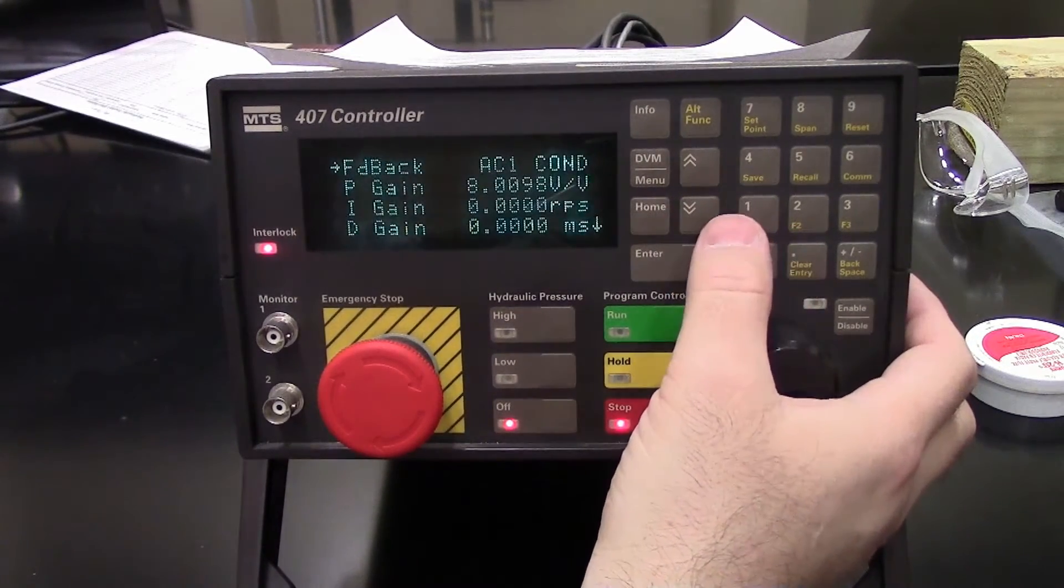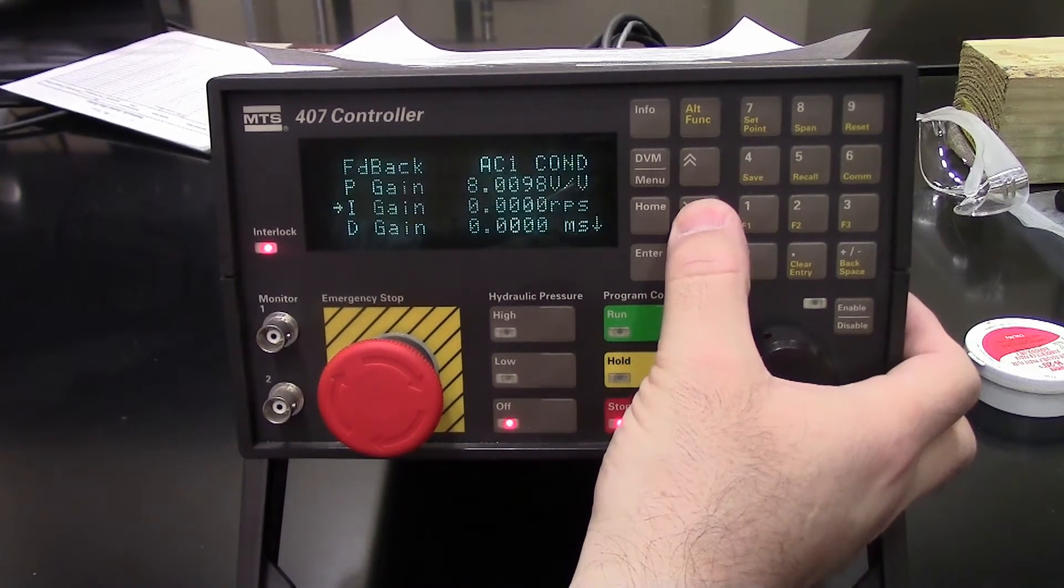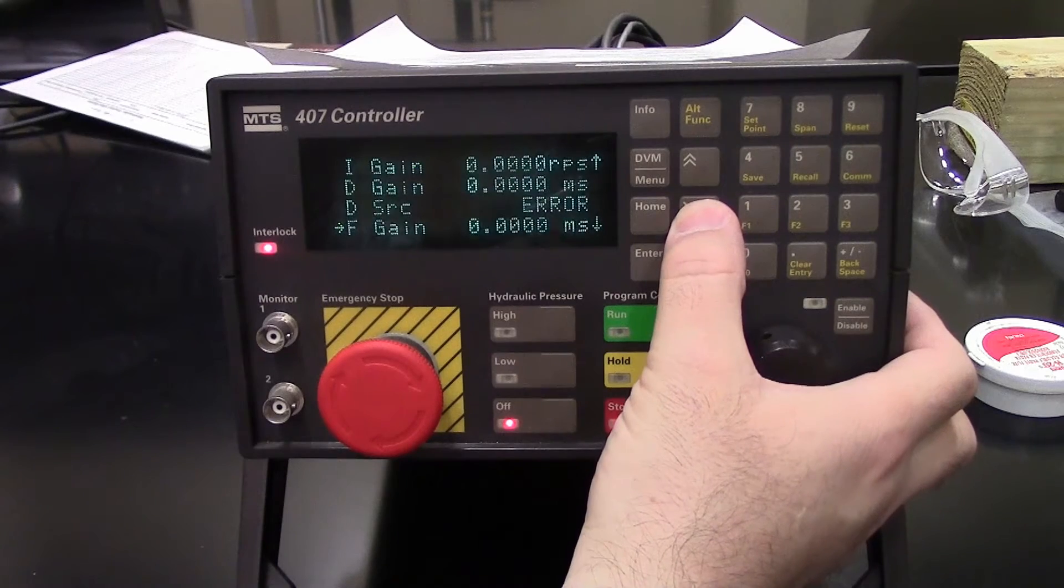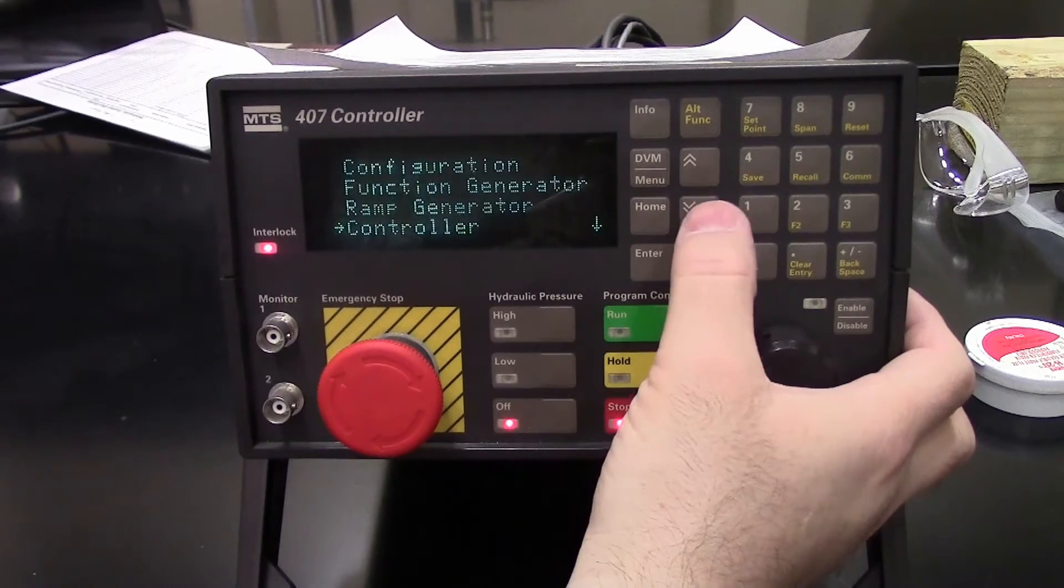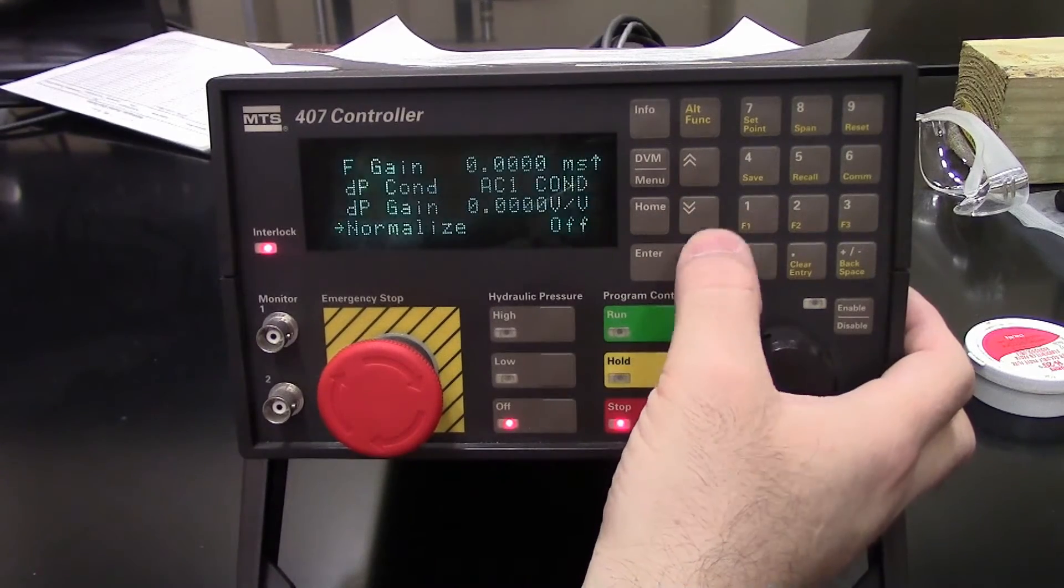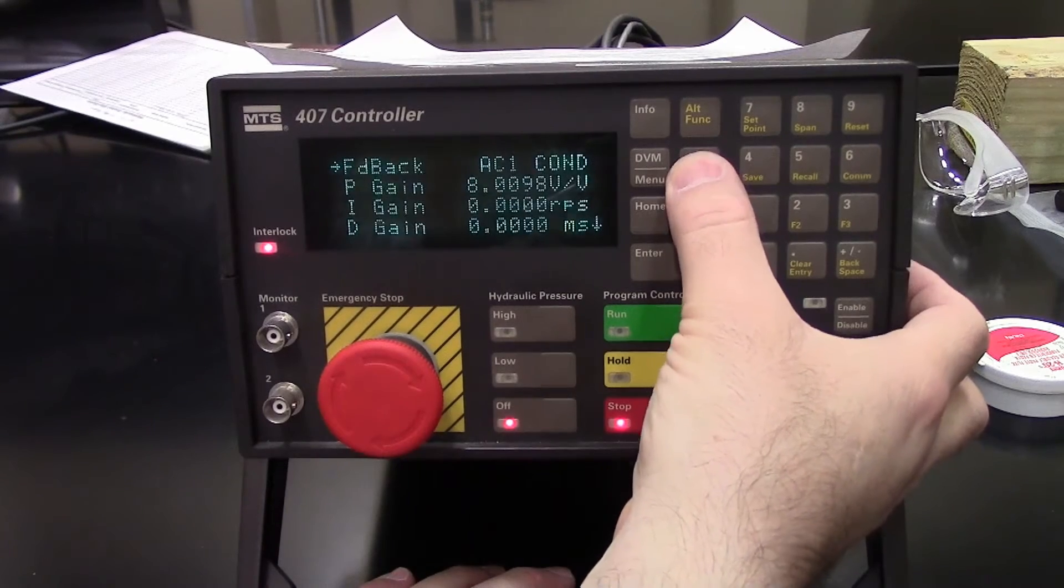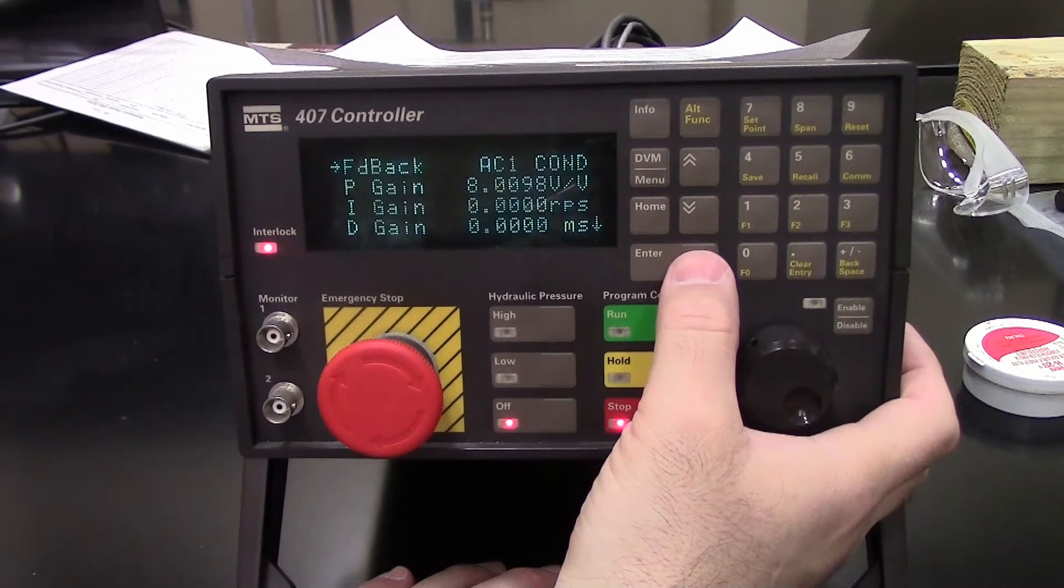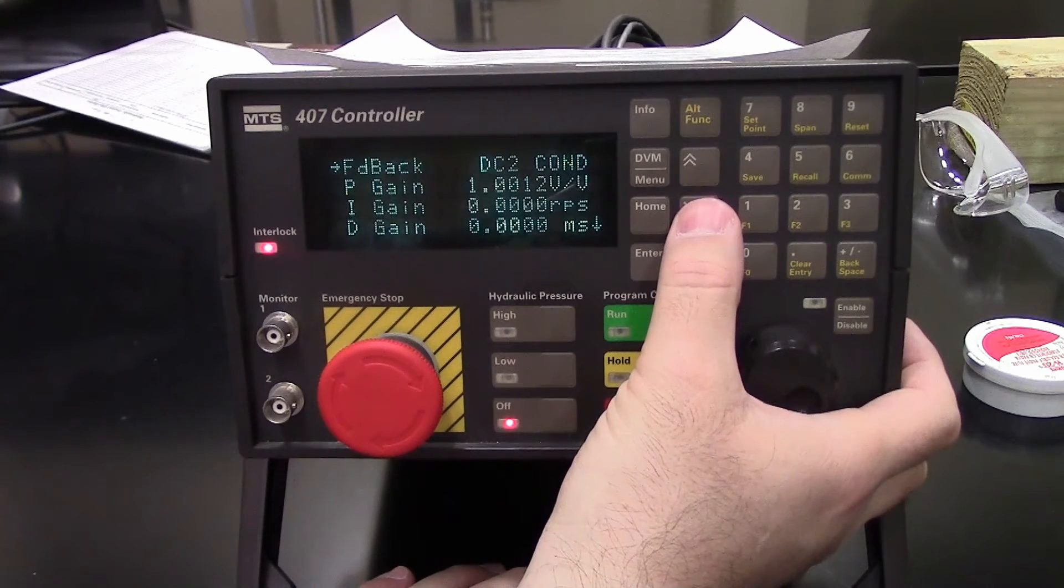Maybe more important is the controller. This is for the AC1 conditioner. Here's the PID gains. Those would change depending on your system. If you want to change this to DC2 conditioner, then you hit enter. This also depends on whether you're in setup 1 or setup 2.